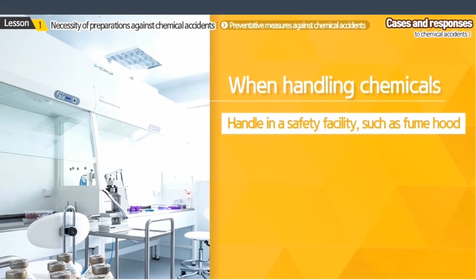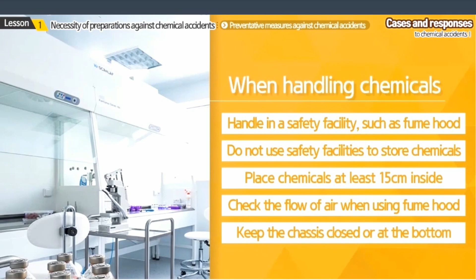When handling chemicals, minimize release by handling it in a safety facility, such as a fume hood. Since it is a space for experiments, the fume hood cannot be used to store chemicals. To handle chemicals in a fume hood, place the chemical at least 15 centimeters inside. When using a fume hood, check the flow of air with a measuring device or tissue. Keep the chassis closed or at the bottom at all times.